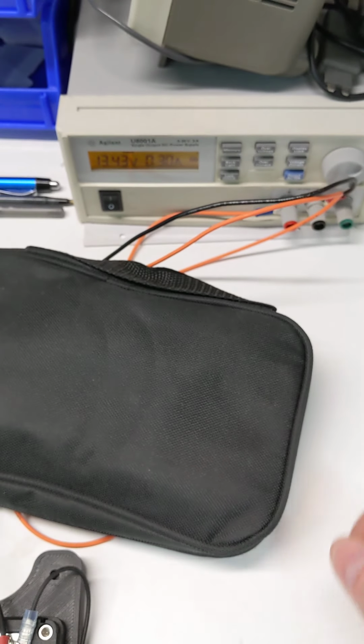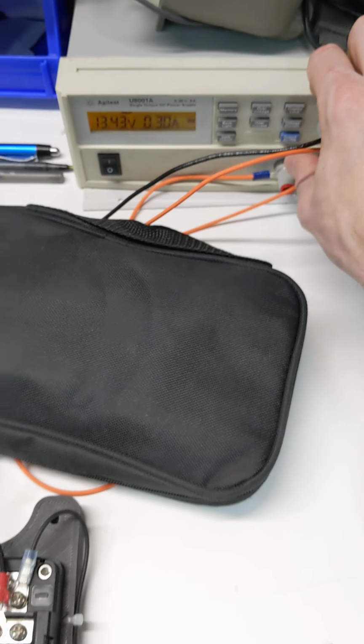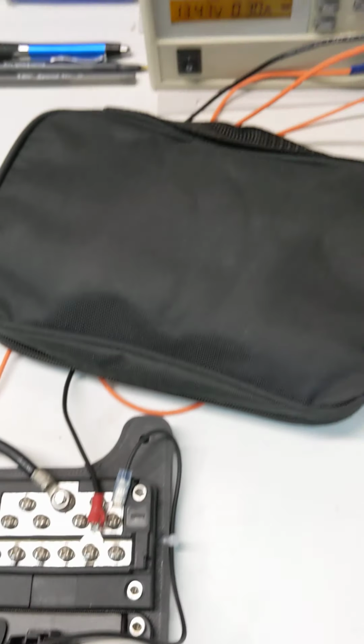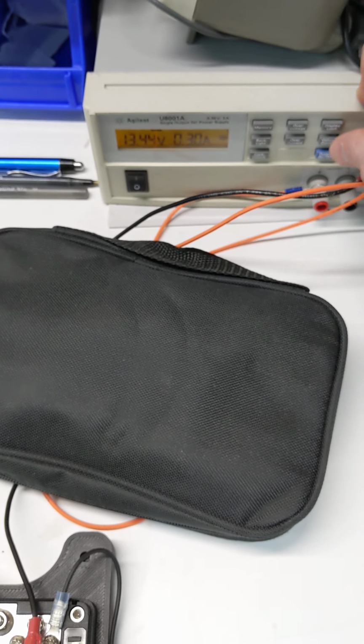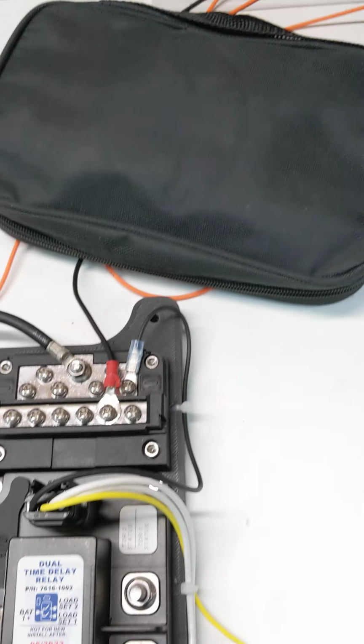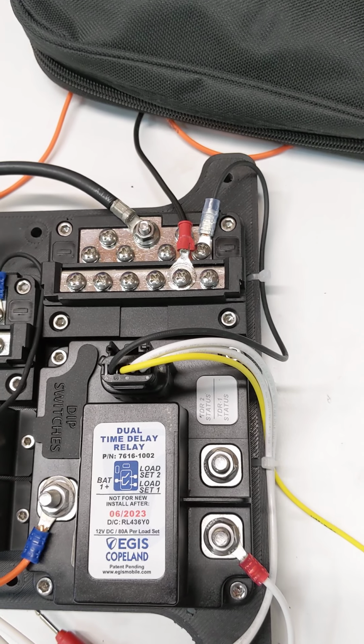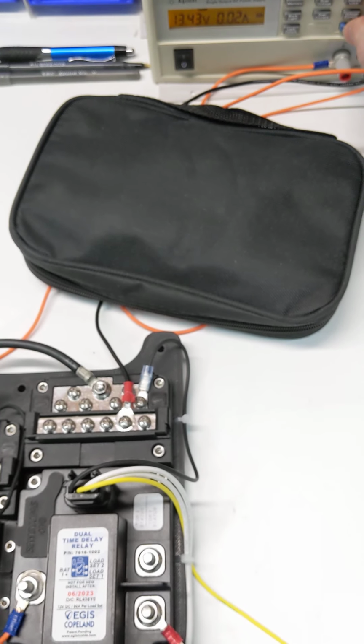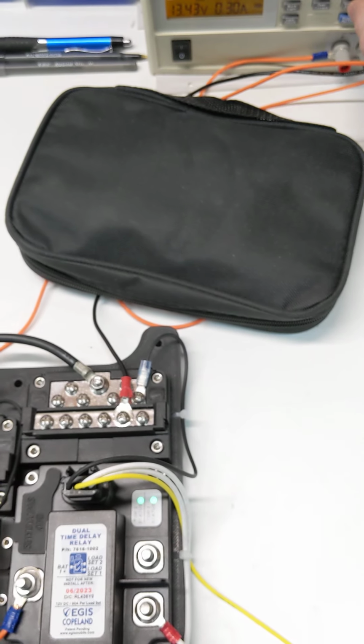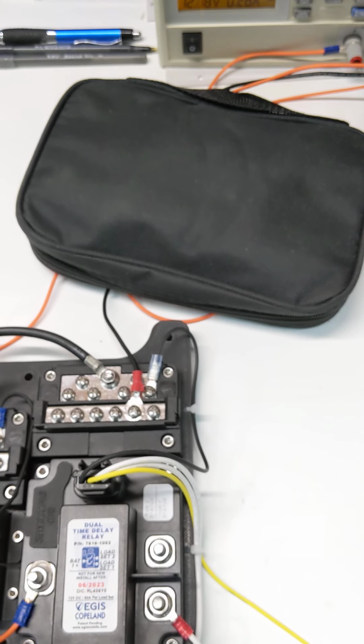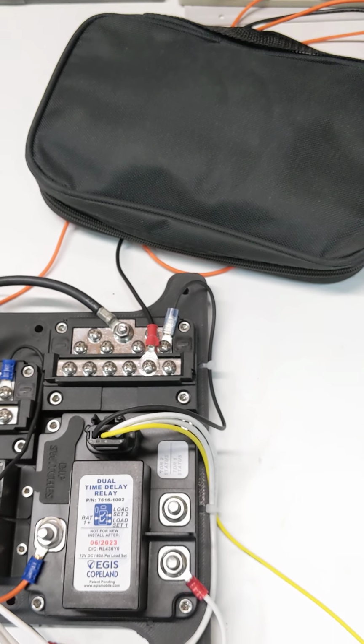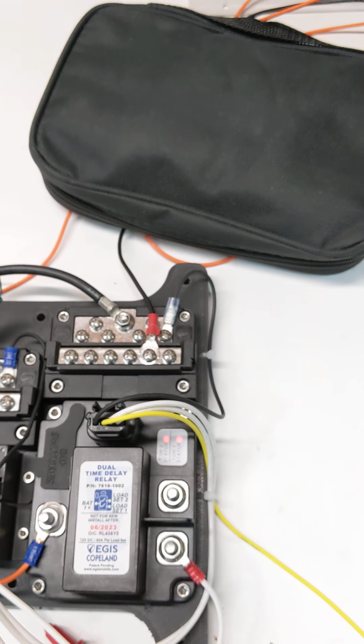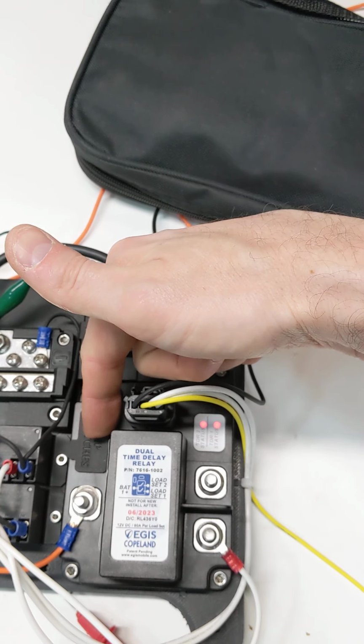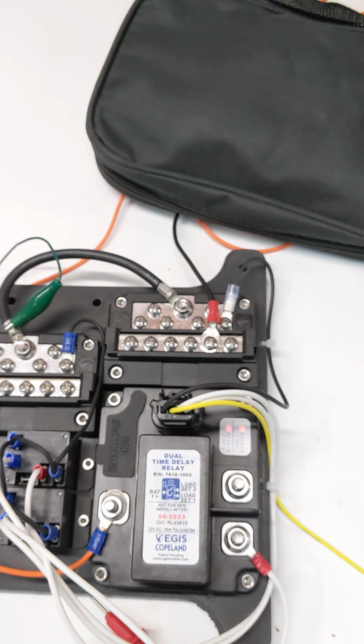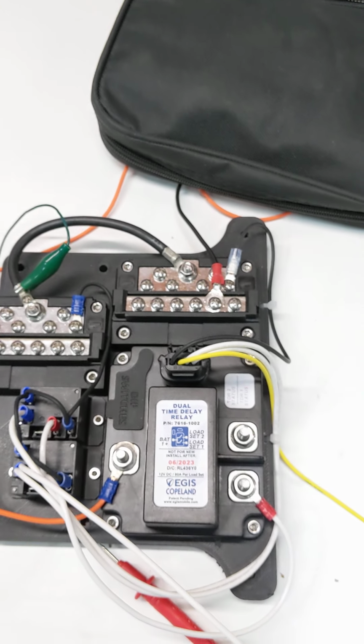What we'll do now is go ahead, and we've turned the device on right now. You can see that this device is green, and then what we've done is we've turned it up to a charge voltage. We'll go ahead and turn the power supply off. Everything turns off because that's the only power to the system. And now we'll go ahead and turn the power supply back on, and then you'll see that the device automatically turns on because it's sensing that 13 volts. If we start turning the voltage down to below 12.7 volts, the device will start flashing red because it's in timeout mode. In this particular case, the dip switches under the dip switch cover here are set to 30-minute time delay. And both 1 and 2 are set to 30-minute time delay.